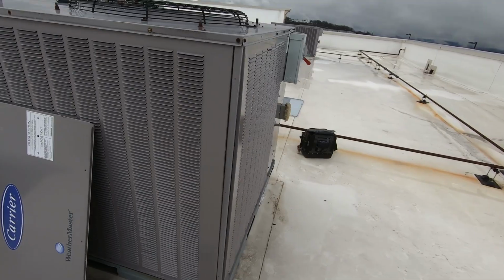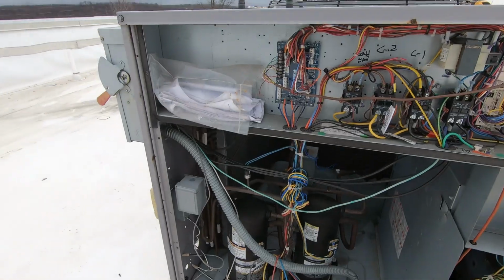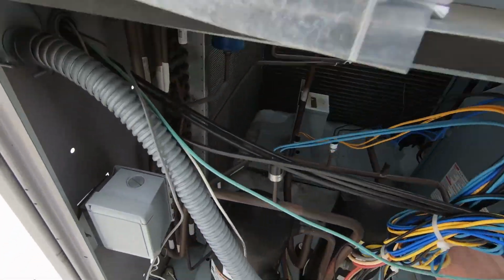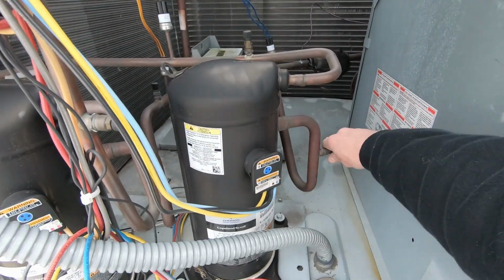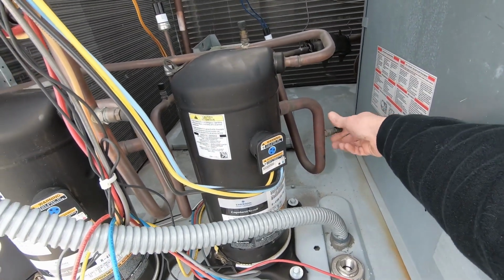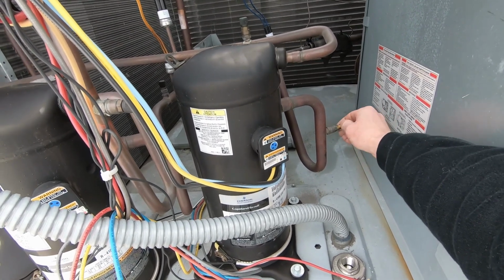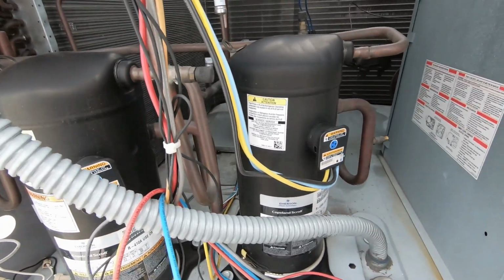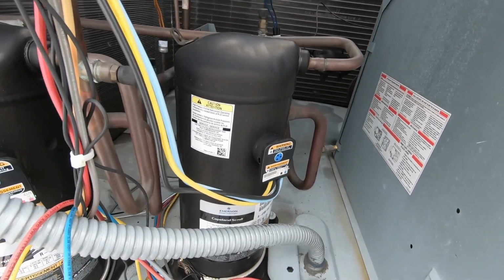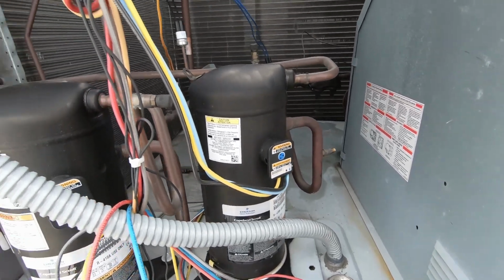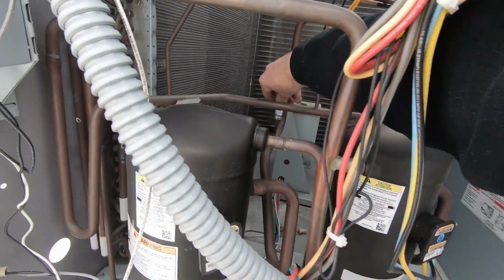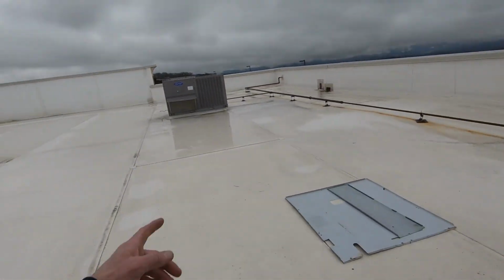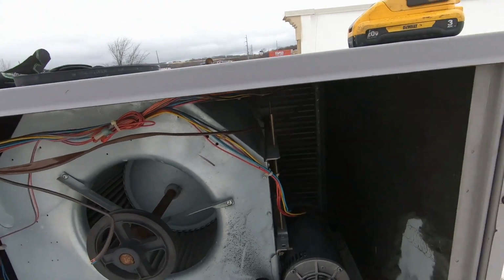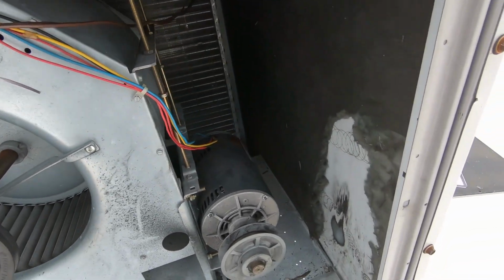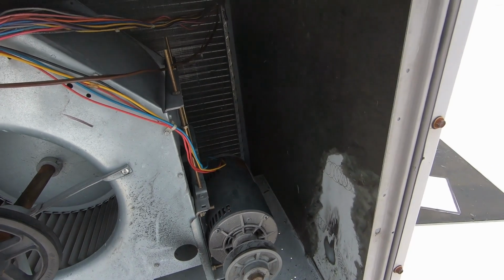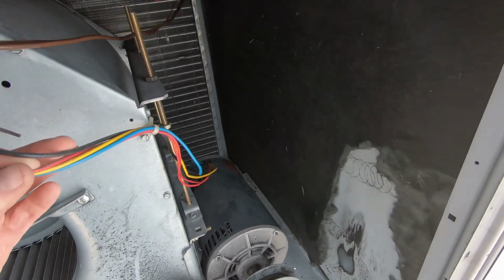If I didn't mention, I drove 2.5 hours this morning to get here. May grab a gauge and make sure that it didn't spring a refrigerant leak. I know these 410A systems are rated for high pressure, but it might be worth my while to throw a set of gauges on them just to make sure nothing's flat now. I am going to cycle that one. This motor just smells too burnt. Like, I can smell it from here. It's cooked. I'm not even going to bother applying power to this thing.